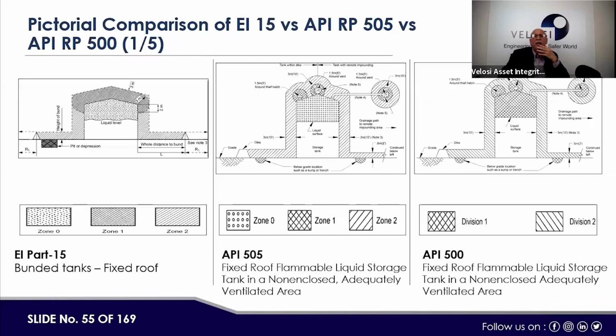Now, if we see the comparison of the hazardous area classification, how we make the shading: in general, zone 0 is dots, zone 1 is double cross, and zone 2 is a single line. Similarly, in 505, dot, cross, double cross, and single line. In the European code, which is EI part 15 or previous IP-15, we take the example of a fixed roof tank. Above the liquid surface, this is zone 0. Then up to 3 meters, and from the top of the tank to 2 meters, this is zone 1. Then below, up to the dikes, this is zone 2.